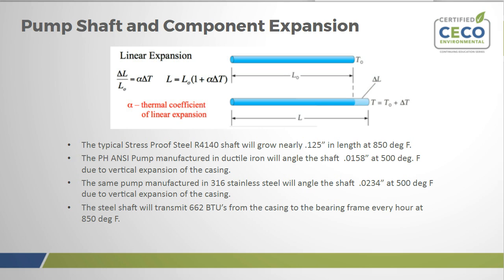Same pump manufactured in 316 stainless will deflect the shaft nearly 23 thousandths at 500 degrees. Once again, due to the vertical expansion of the casing itself. A steel shaft will transmit about 662 BTUs from the casing to the bearing frame every hour. And this presents a problem because now you're heating up the bearings and you're heating up the oil and the lubrication aspects of the pump. So all these things need to be taken into consideration when you're actually designing the pump itself.